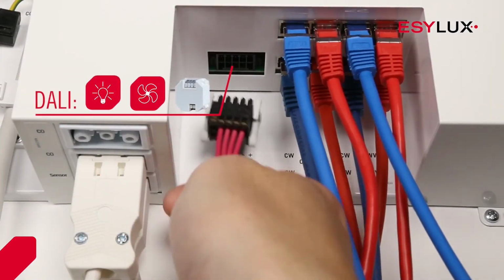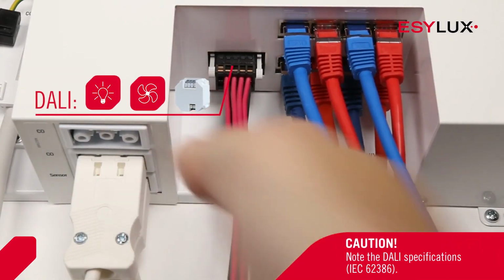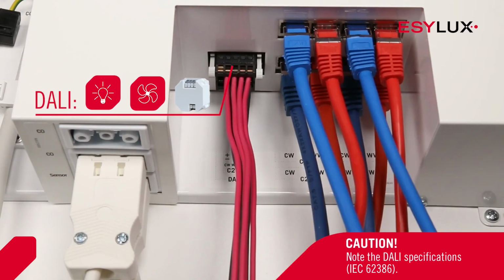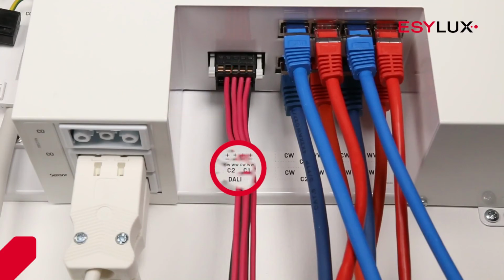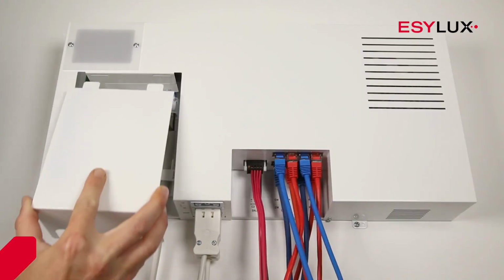Where necessary, Dali devices, including Dali switches, can be connected via Dali interfaces C1 and C2. The Dali interfaces are assigned to both the channels at the factory. Up to 25 Dali devices can be connected per channel. The cover can now be screwed on.